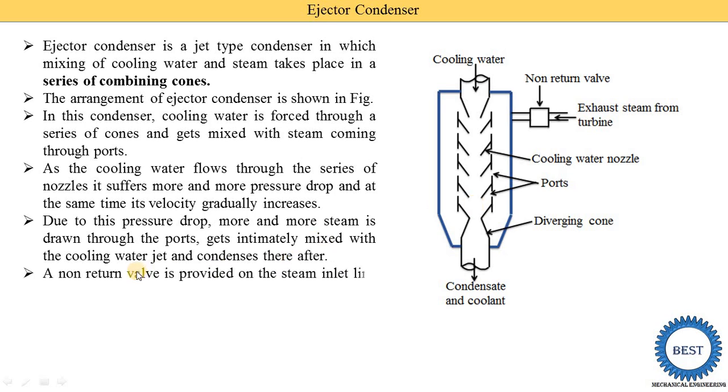A non-return valve is provided on the steam inlet line to prevent the backflow of condensate in case of failure of cooling water supply. Here you see in the steam supply line, the non-return valve is put. Non-return valve means the steam is not supplied back to the turbines.